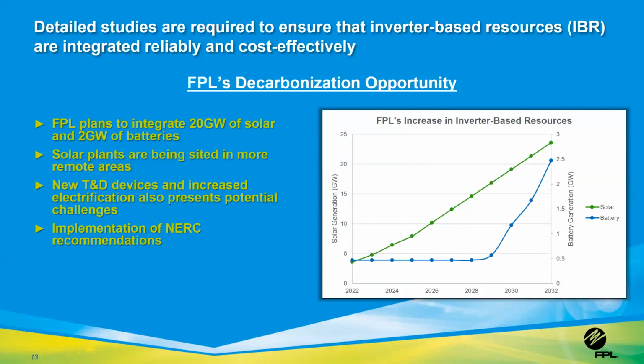So Florida Power and Light currently has approximately 4,000 megawatts of solar installed and 500 megawatts of batteries. But our resource plan calls for us to increase those amounts six-fold over the next 10 years. By reference, our peak system load is currently 27,000 megawatts, and we're planning to have almost 24,000 megawatts of solar by 2032. This means that the instantaneous penetration of IBR will exceed 90%, many times throughout the year.